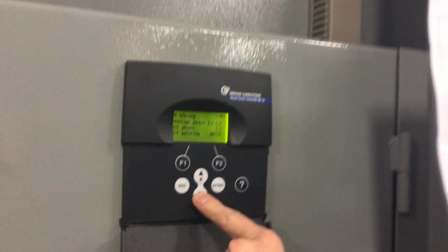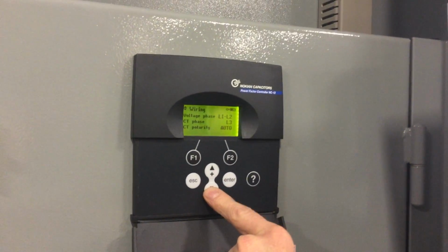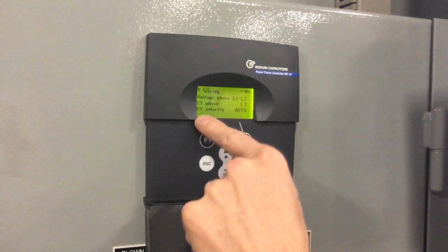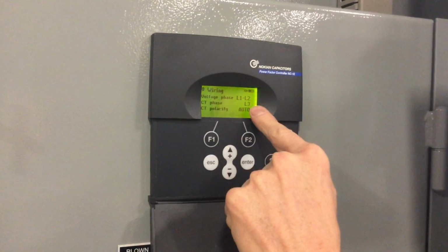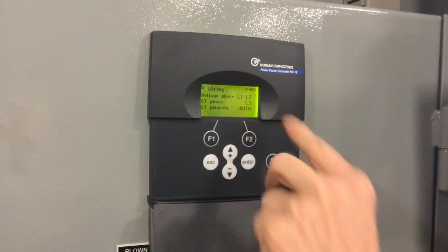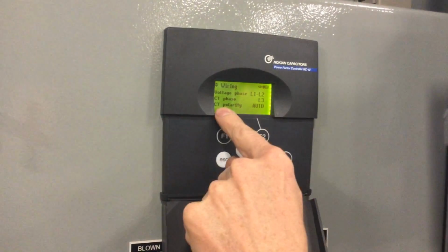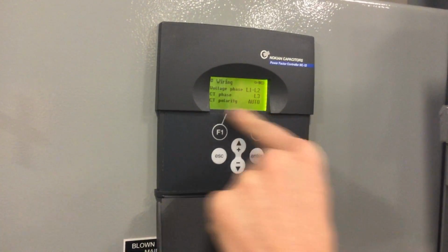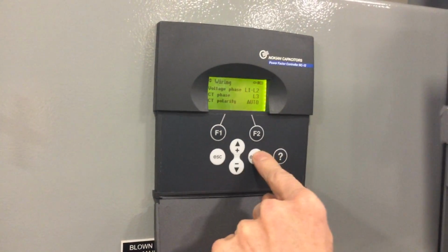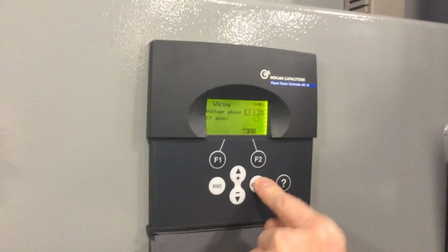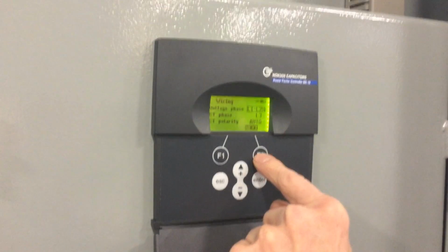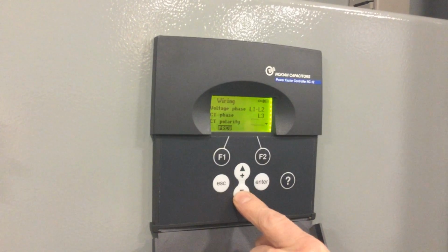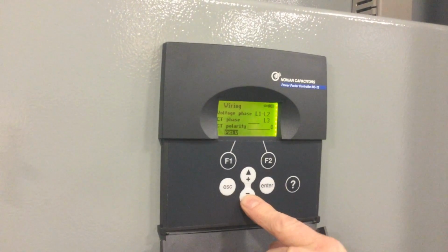This is telling us how you're connected to the three-phase network. In this case, we're getting our voltage reference from line 1 and line 2, phase to phase. That would be phase A and phase B. The sensing CT is placed on C phase, L3, and we can select the polarity of the CT. And we can toggle between automatic, reverse polarity, or direct.